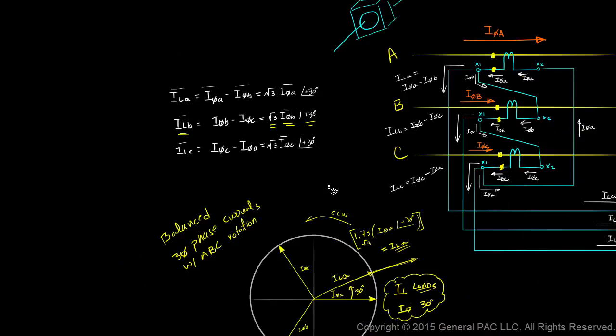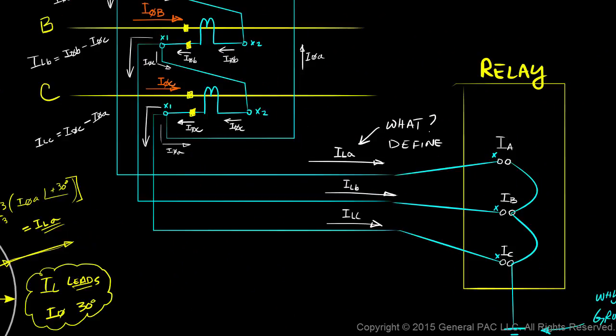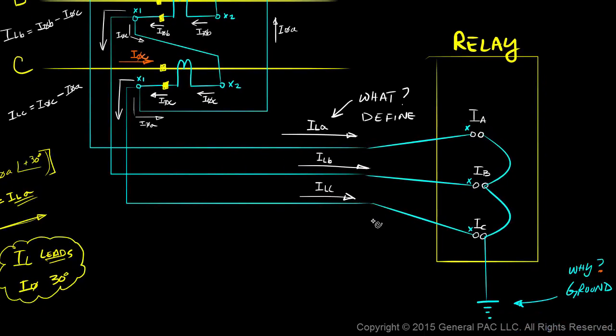Alright, so the last part of this video is essentially what happens to this line current. Now that we've defined this line current, what happens to this line current when the non-polarity side of our input terminal are connected like this? Okay, so we know that line current a is going into the polarity side of the input terminal for phase a. Which means line current a is also flowing out of the non-polarity side of the input terminal. Similarly, the current that's flowing out of the non-polarity side of our phase b input terminal is line current a plus line current b.